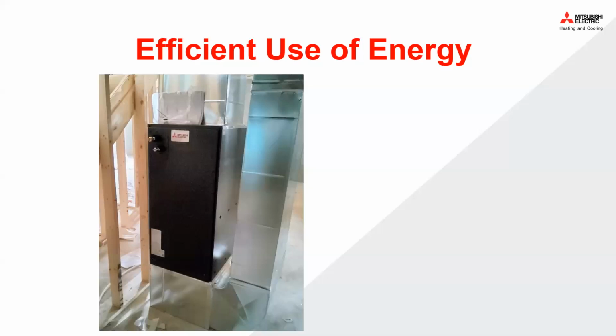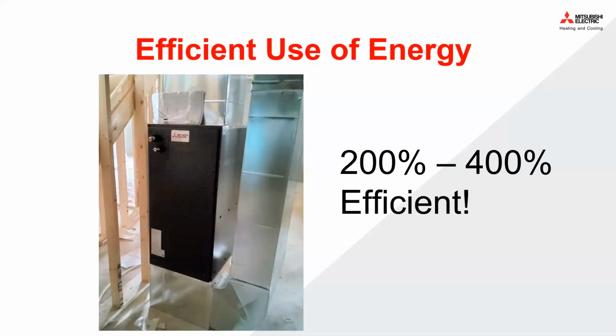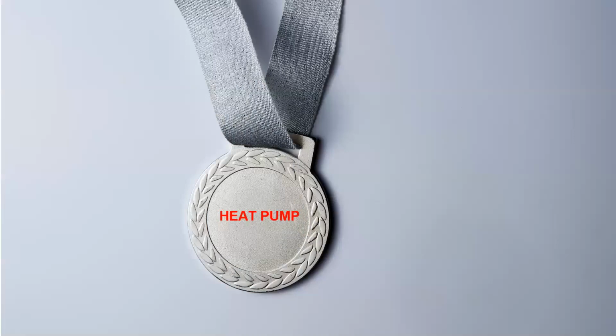And then we have the subject that we're talking about, heat pumps. Because the heat pump doesn't have to use energy to create heat, it's the closest thing we have to creating energy. So back in high school in physics, we learned the first law of thermodynamics: energy can only be transferred from one system to its surroundings or vice versa. It can't be created or destroyed. We can release it, we can convert it, we can store it, and we can transfer it. And this is what heat pumps do very well. They transfer heat from one space to another. The other qualities that make a heat pump the champ over traditional systems are their ability to vary their capacity with a large turndown ratio and their ability to reverse their cycle to provide heating and cooling.